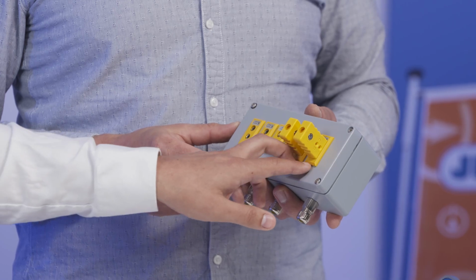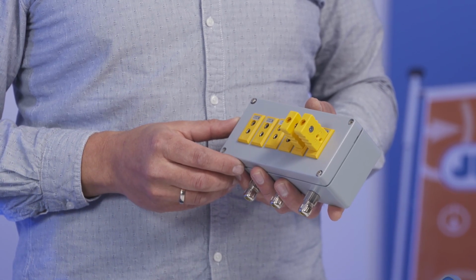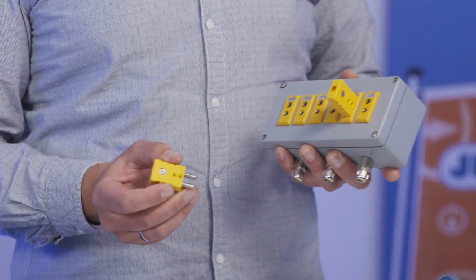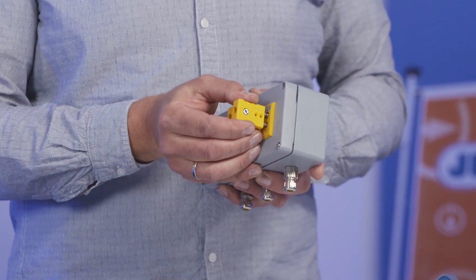Yes, the values. So I think what we did here is put the connection in parallel. When you do the testing and you take out the thermocouple and then test with your calibration device, no error comes and no value is missed, because when the value is lost, normally the thermoprocess furnace breaks down and gets an alarm, right? And then you have trouble with shutting off the burners, and then the whole batch pretty much is ruined. Right. Or the temperature is lower, and so you must wait until the temperature is at the right position. So it's easier to use the thermobox.